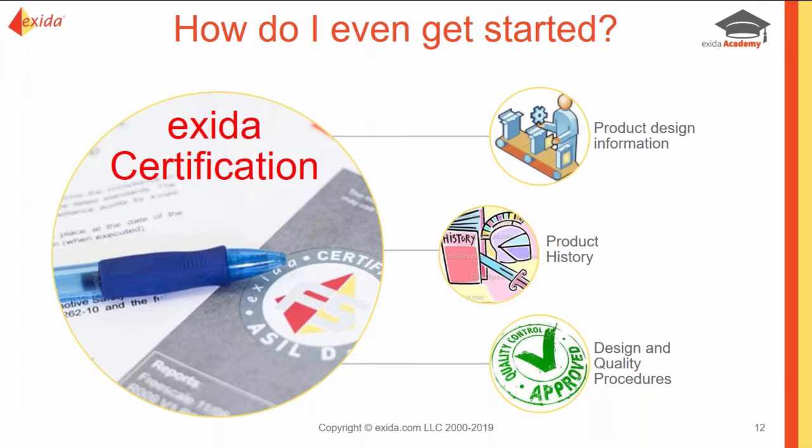That third party assessment is going to look at all of the standard's requirements, looking at your detailed analysis of engineering, the processes, the procedures. We're going to determine your systematic capability. We're going to look at cybersecurity if you have software and that's needed. If you're a simple mechanical device, obviously not. We're going to look at detailed strength analysis, hardware designs. We're going to look at design margins, random failure rates, the different failure mode analysis, testing.